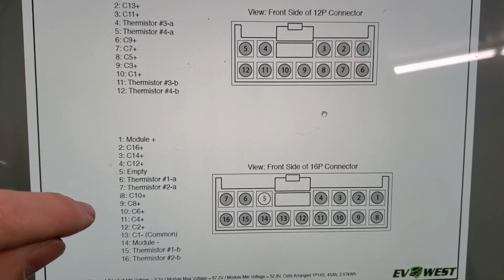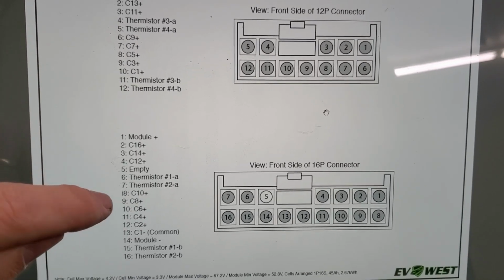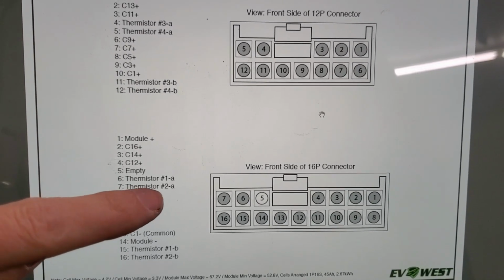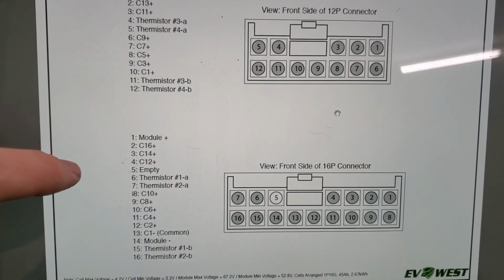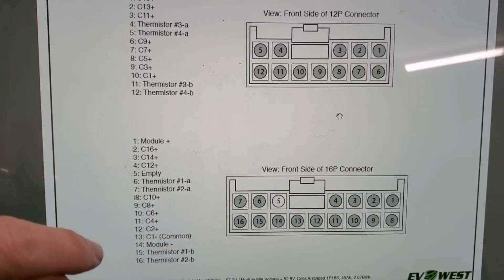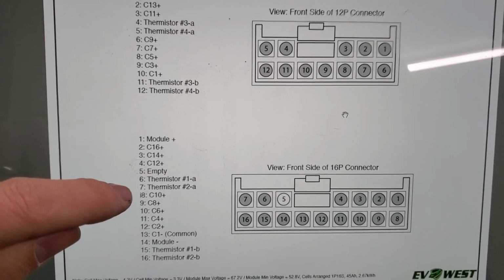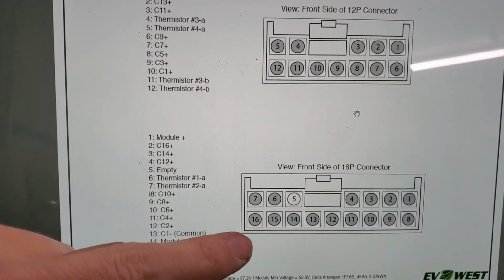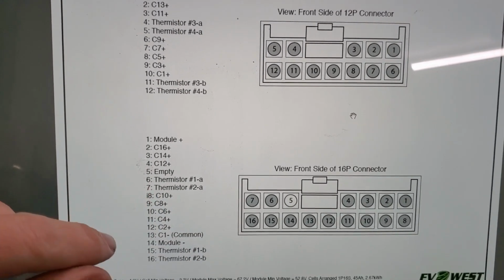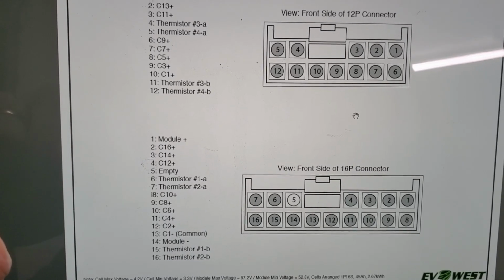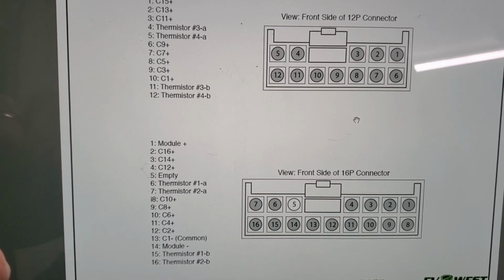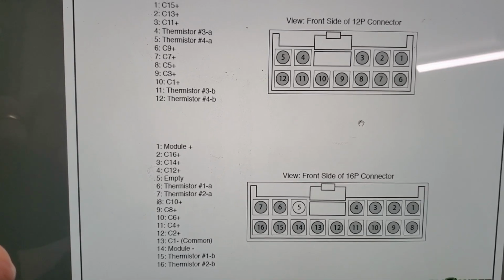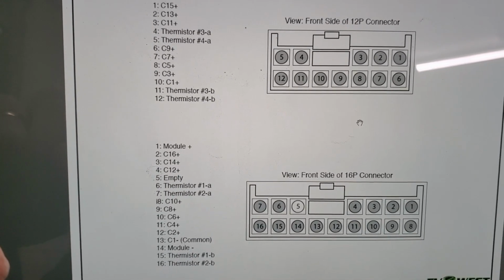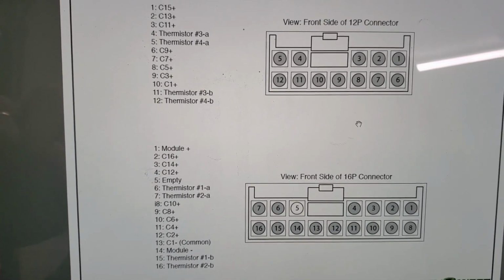All right, here's the pinout of the battery modules. For my wiring, I chose pin 7 and 16, which is thermistor 2. I'm going to switch it to pin 6 and 15, which is thermistor 1, and see if the software will pick it up. If the BMS will pick up that thermistor reading, because I did the continuity check for the wires and everything seems good.